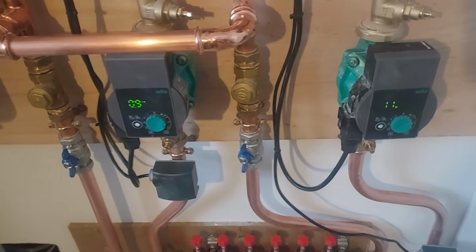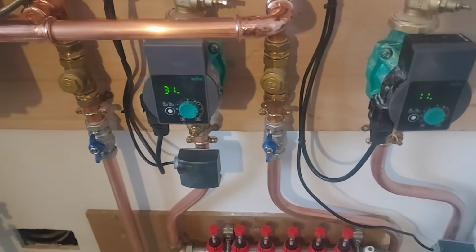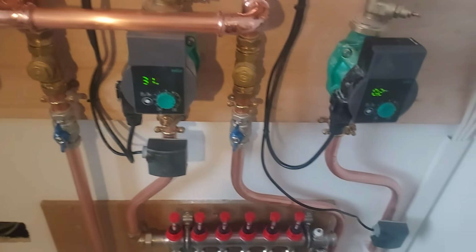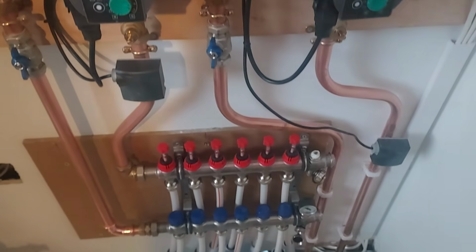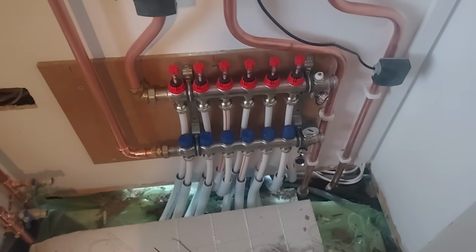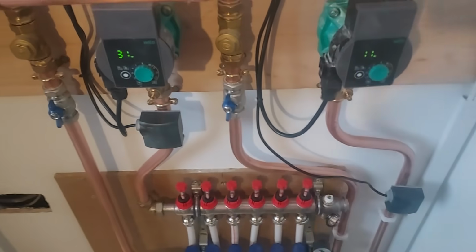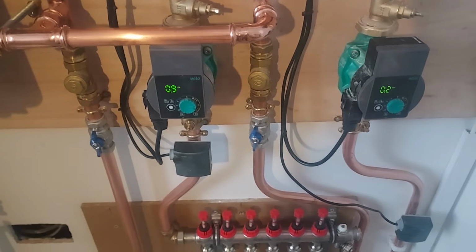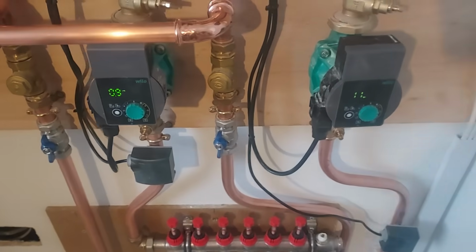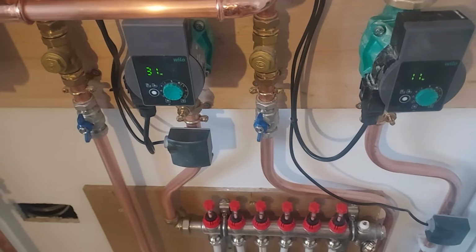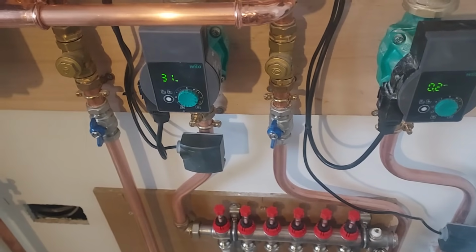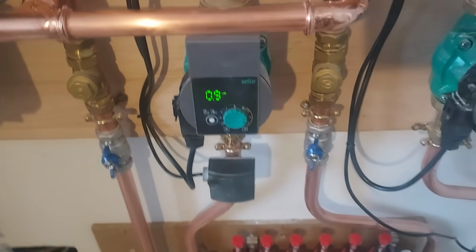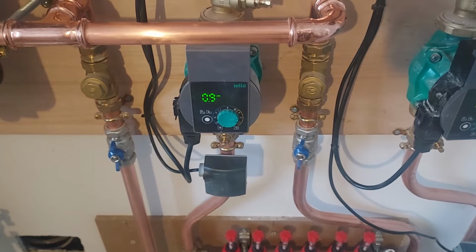So where I need 1.5, for example, I've set to 2, and where I need 0.85, I've set to 0.9. So it's slightly higher head than required, slightly higher flow rates on both circuits than required. And that would allow us, as we go around, to balance up and make our adjustments. We'll lose a bit of flow off of those pumps. Now, it does also give us the consumption in watts, and that also allows us to make a judgment in meters head as well.